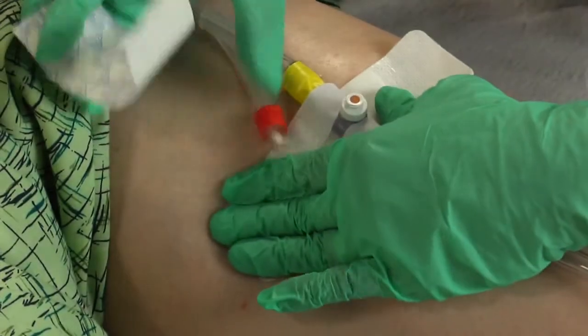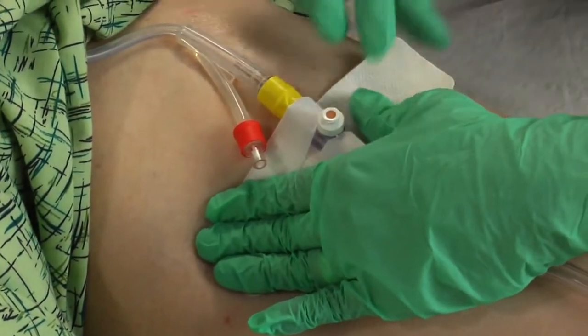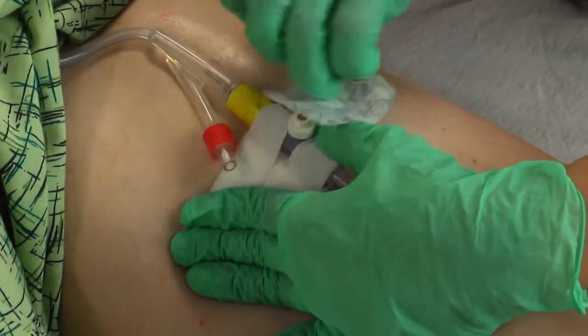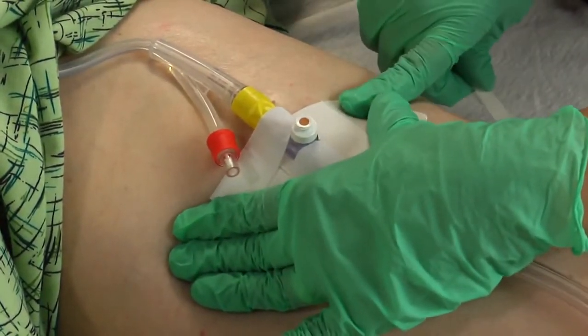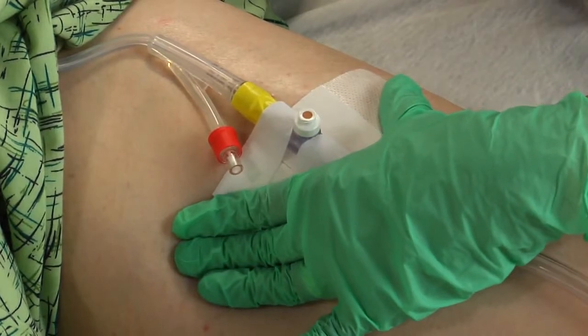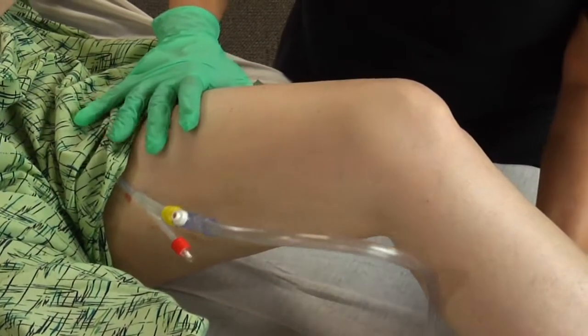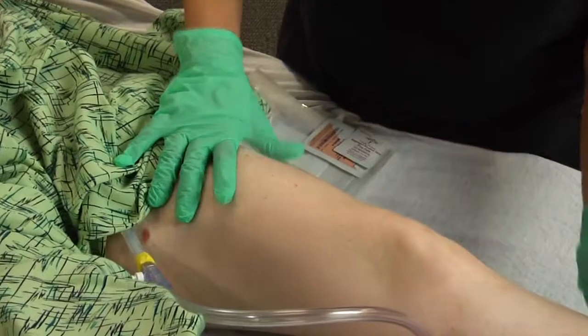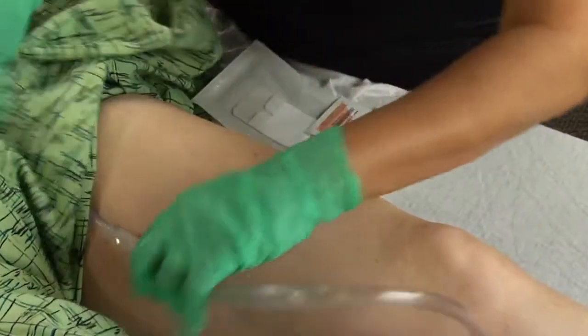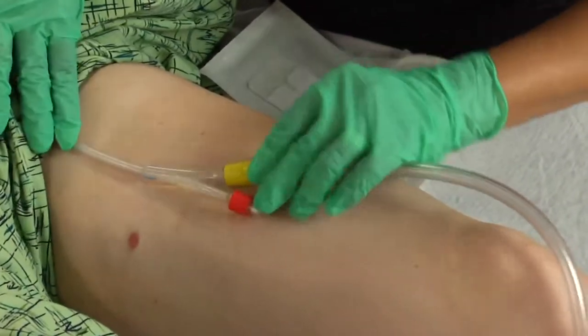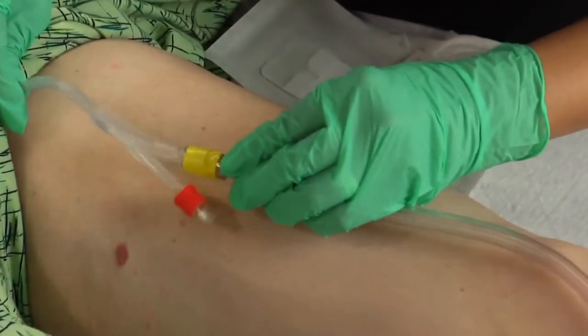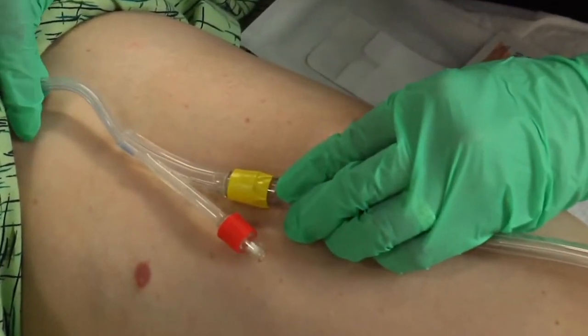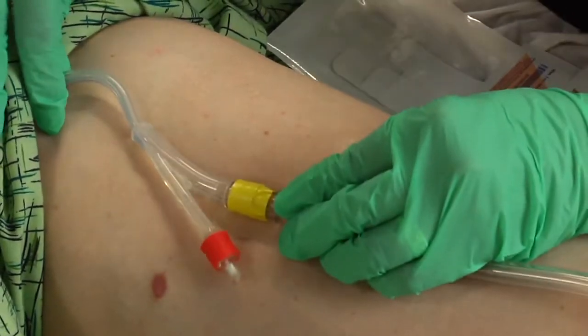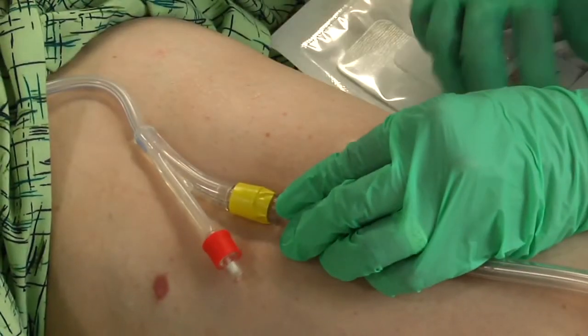The catheter securement device should be placed on the patient's high thigh or abdomen to prevent the catheter from causing unnecessary damage to the skin, bladder neck, or urethra. To apply, straighten the patient's leg, then pull gently on the catheter so it lays completely straight along the thigh. Once the catheter is straight, move approximately 1 to 1.5 inches up the leg towards the catheter tip. This is the area of the patient's leg that should be prepped for application of the device.